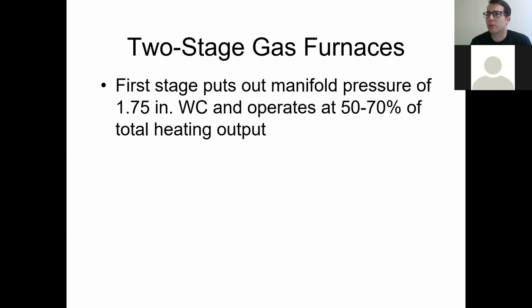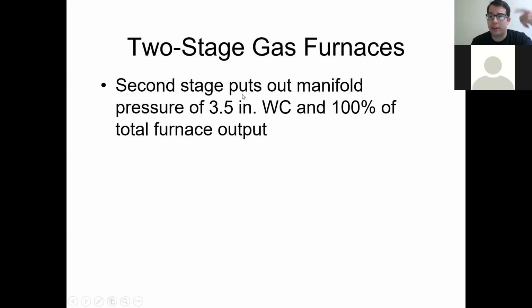She's fine. Sorry. 3 to 3.5 inches of water column. So this is about half of that pressure. 3.5 divided by 2 is about 1.75. So this makes sense: if it's going to go into half speed and half heat, it's going to be half gas pressure. That was the nice thing about these manifolds and how the gas valve was able to not just turn on and be all the gas at one time. It would actually control only 50% of the gas or 100% of the gas. And you see here it's saying 50 to 70, which just depends on the manufacturer and how it was first assembled. So second stage, like I said, is when it's going to go full. It's going to go to that 3.5 inches of water column, just like we would normally see coming out of the output side of any other gas valve. So that's our full pressure.